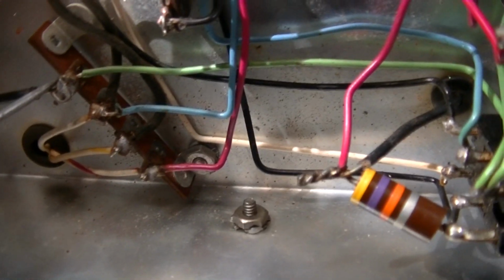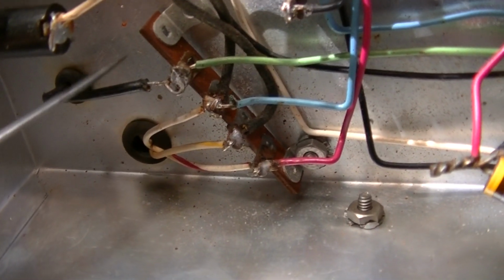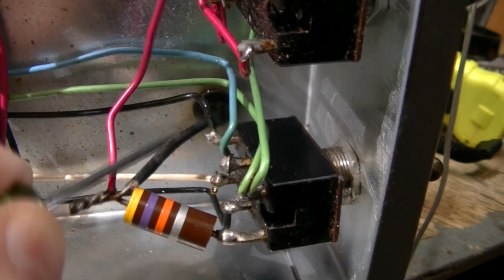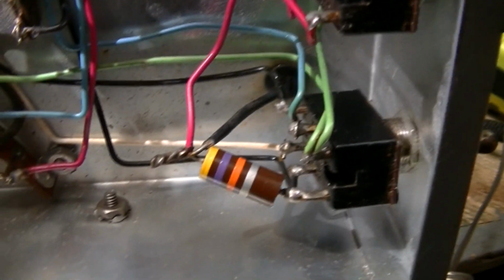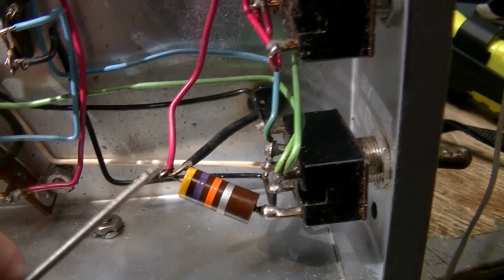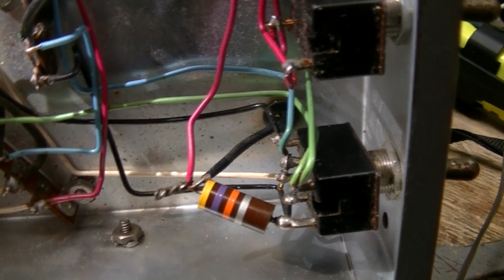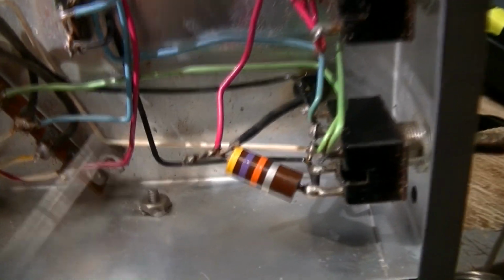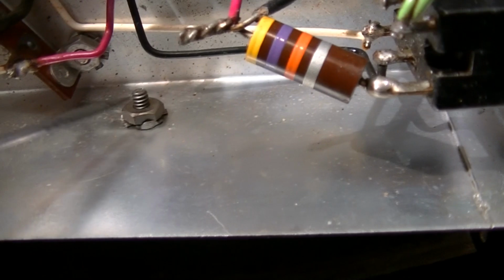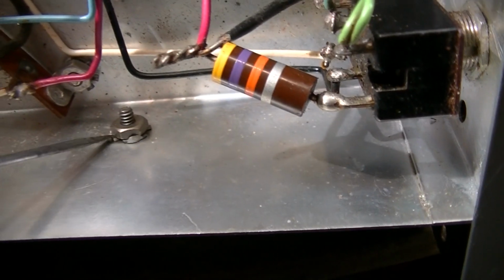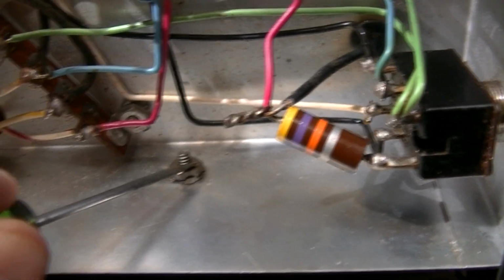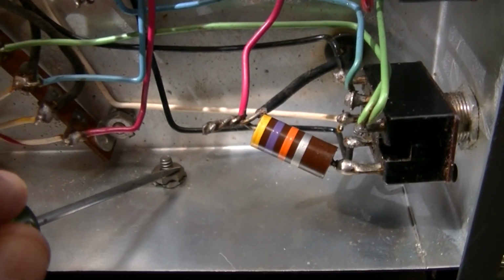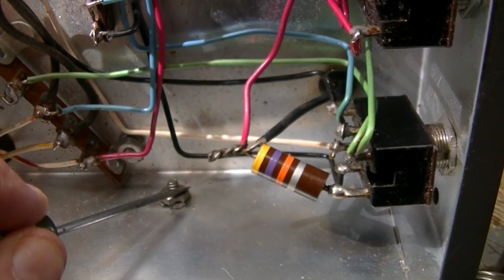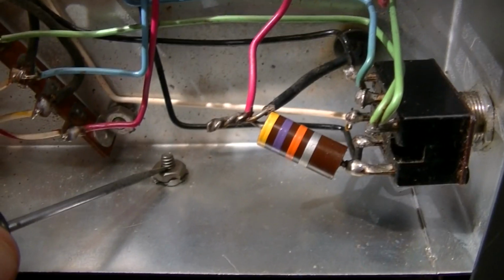Now I put a voltmeter on here on the negative. This is the negative of the electrolytic I showed you on the other side, 12 microfarad, and the positive is right here, this is the other lead. I put a voltmeter across it, and when I cranked up the variac, I got 504 volts across it. So what I want to do is take the clamp off, loosen this nut, and take the clamp off so I can read the voltage rating of that electrolytic. As old as it is, it's holding 500 volts, so it won't need to be replaced.